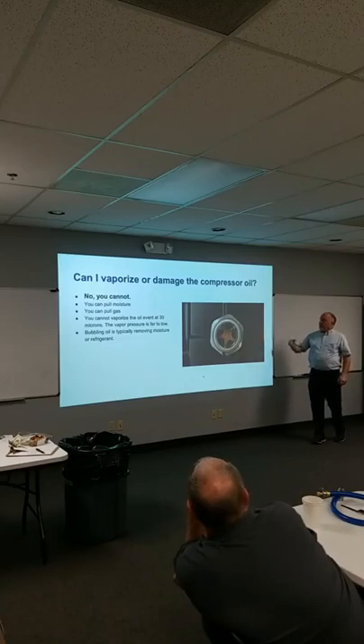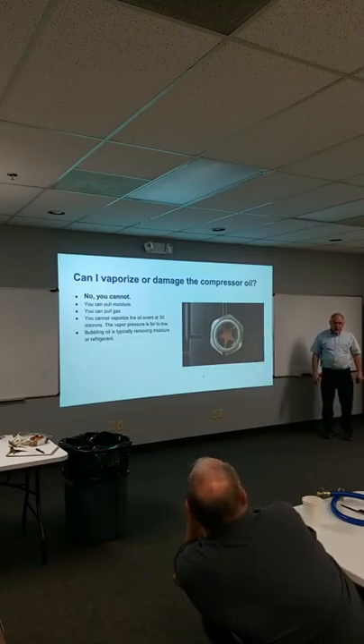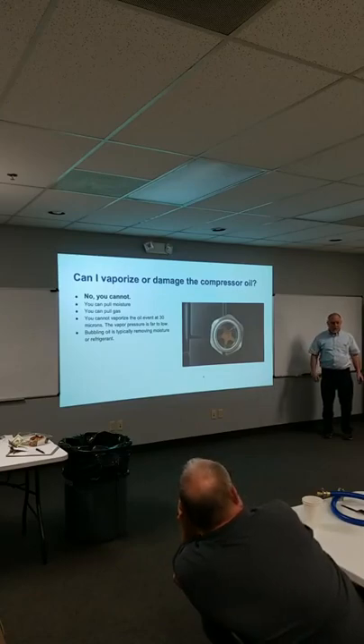Can you vaporize compressor oil? This is one I hear all the time. JB's got some great wrong information out there on this. They're like, never pull below 200 microns or you'll vaporize the oil. Well, no, you can't vaporize the oil. If you ever want to find out yourself, just go get some POE oil or some mineral oil, pour it in your vacuum pump and put your vacuum gauge on it.